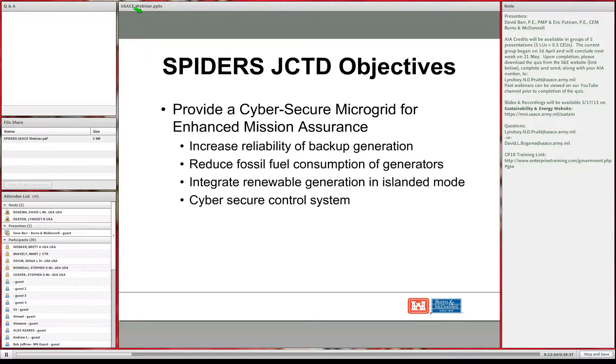During Q&A, a question was raised: if microgrids rely on diesel generation, how do they help the Clean Energy Act? The answer: a purely renewable microgrid is possible with reliable sources like geothermal or with significant battery storage to compensate for solar and wind intermittency. In reality, net zero means sometimes exporting and sometimes importing power, averaging to zero over a year. The generator doesn't have to be diesel—it could be natural gas, biofuel, or biodiesel combined heat and power—but something reliable and fast-responding is needed as spinning reserve.